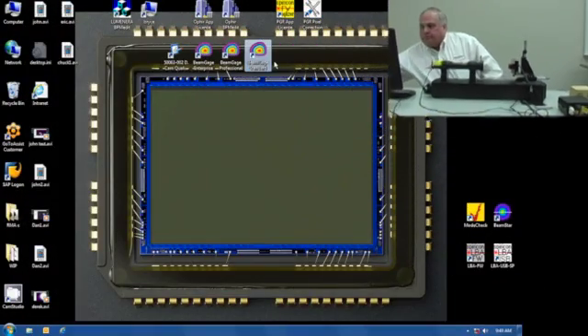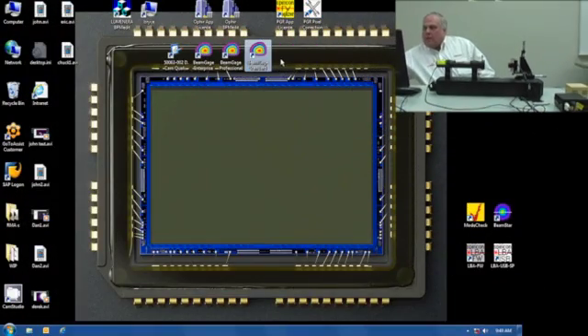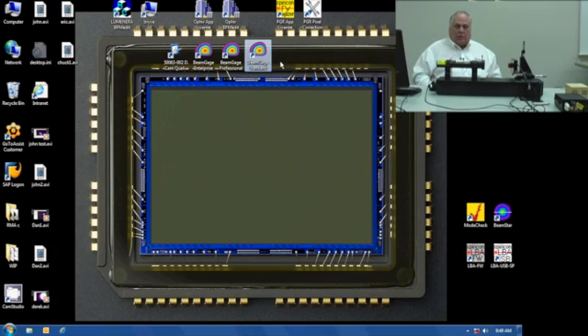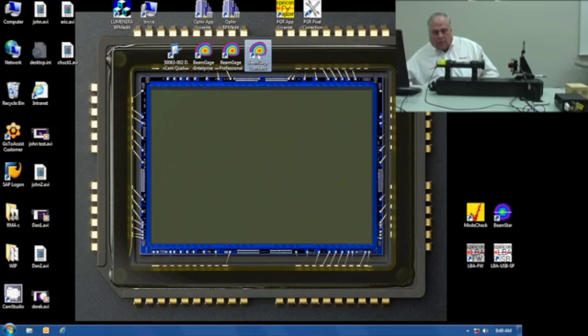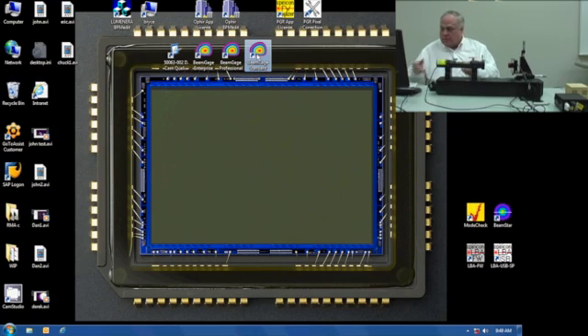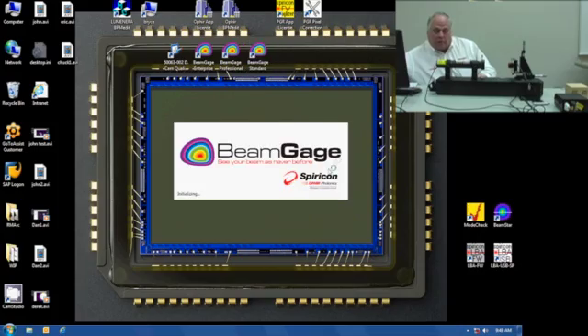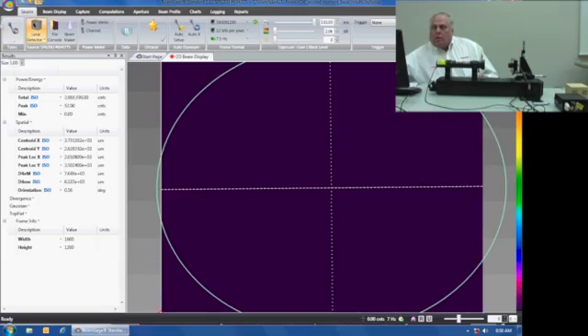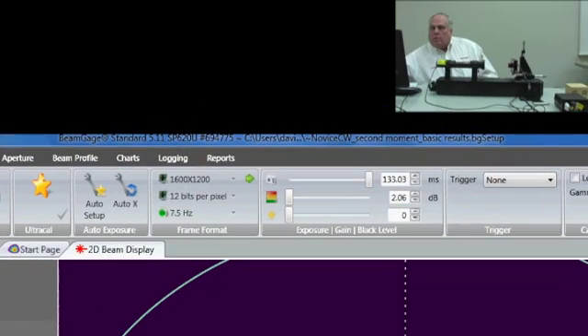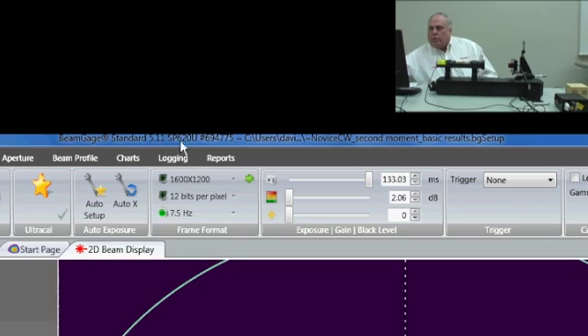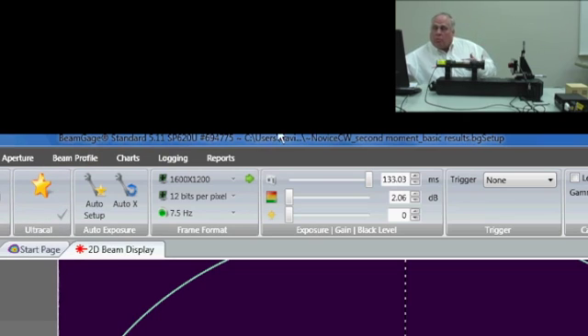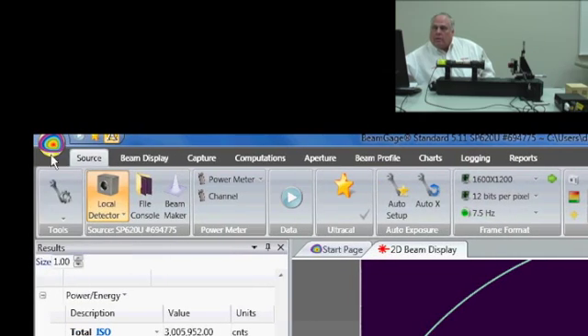What we're going to do here, I'm going to go to the basic software setup just to get the camera turned on and get you ready to go. You've already installed the software with administrative privileges. I'm going to go to BeamGage Standard and turn on the software. What you want to do when you first start, you want to double check the numbers at the top. The proper software is BeamGage Standard right up here. The version you're using, the camera itself, here's a serial number and right here's a particular setup file I happen to be using today. When you first turn on the camera, you won't have a setup file loaded probably.